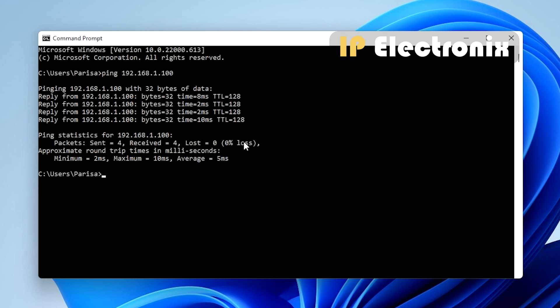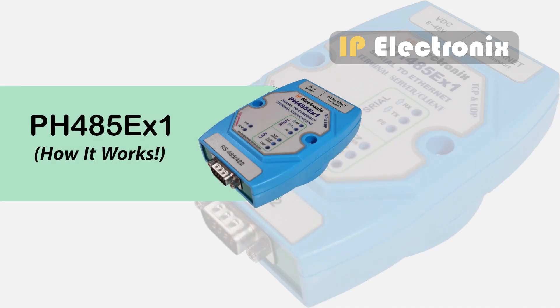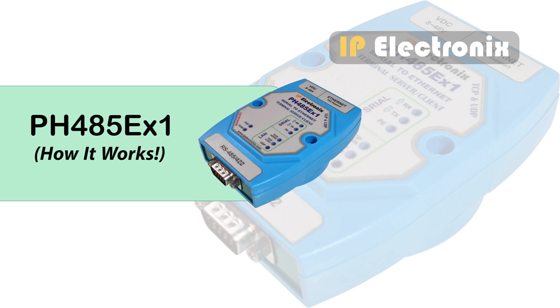If you didn't receive correct response in the ping test, you can't continue working with the device. Didn't receive response could be related to the network settings of the converter or the computer. For example, the subnet mask of the computer and the converter doesn't match. Also, the activation of the computer's firewall can cause no response from the ping test. Finally, if you didn't receive a response, it is better to consult with your network administrator.